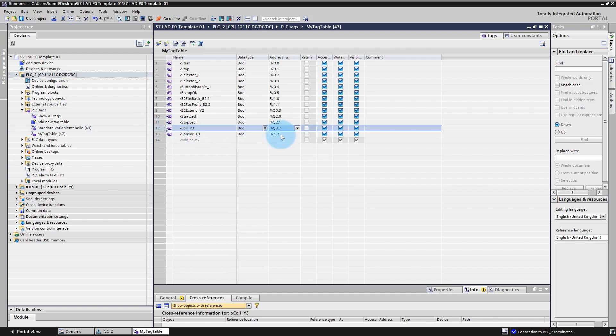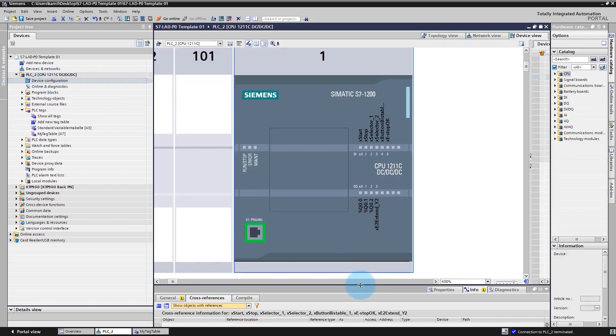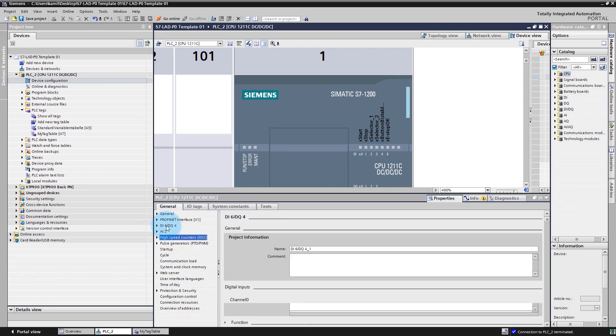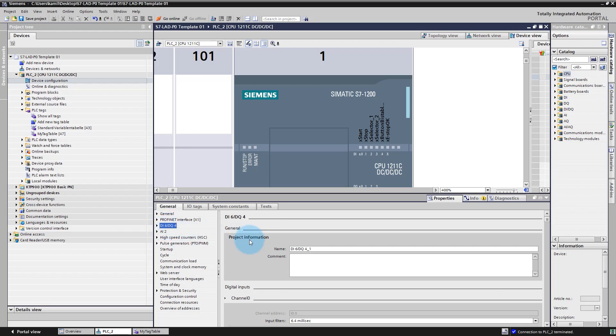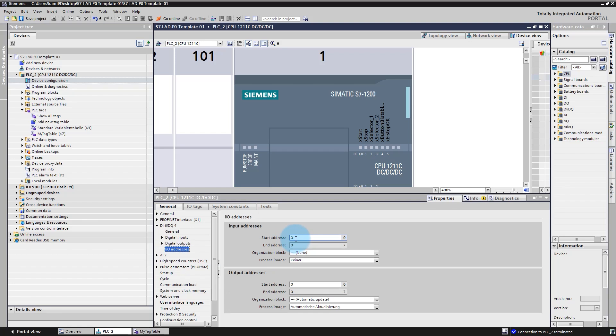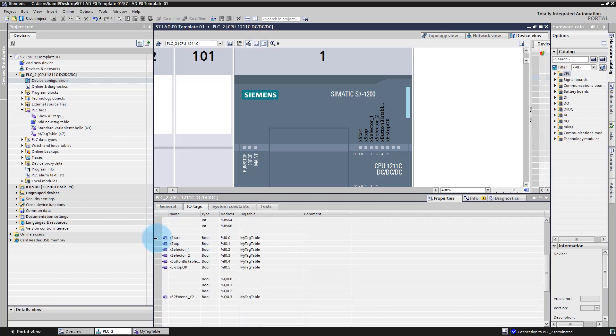How can we find the address — the byte number and bit number — for a variable? How can we check what the address of the physical channel is? You can go to device configuration, then to properties, then general, digital inputs, digital outputs, and I/O addresses. Here you can assign the start address for inputs and start address for outputs. Once you assign those addresses, you can go to I/O Tags and check the addresses of the proper channels in this module.